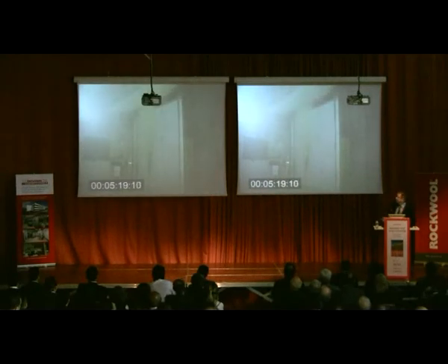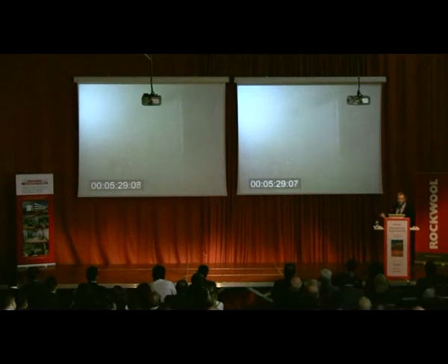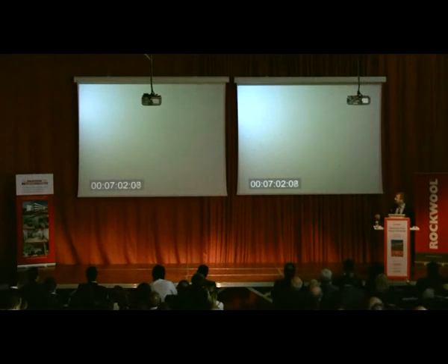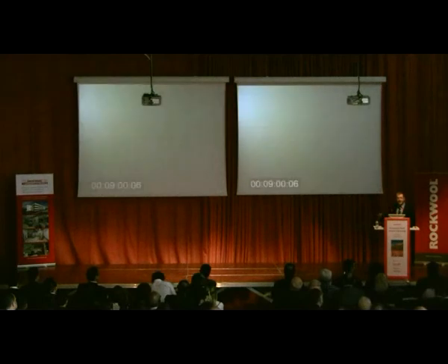So what are the criteria which we evaluate? We evaluate temperatures on the surface, we evaluate integrity, we are looking for small flames, but we don't care about smoke at all in this. So now this will be going much quicker, 5 minutes, 7 minutes. And in spite of the fact that the laboratory got air inlet and outlet and a strong ventilator, strong fan, it was just not possible to get all these gases out of this test hall.